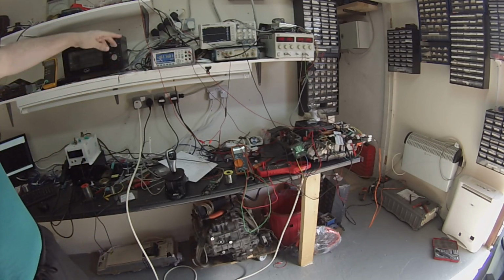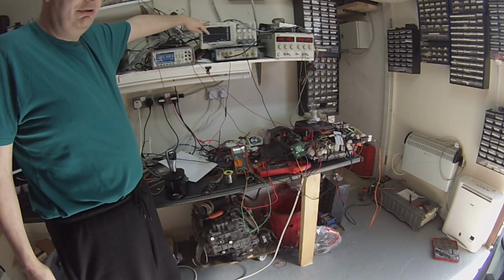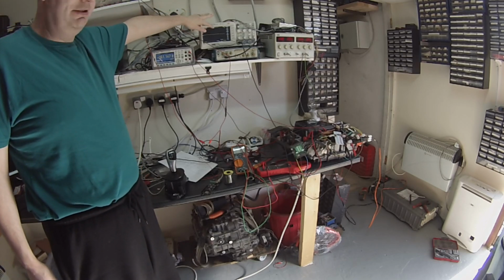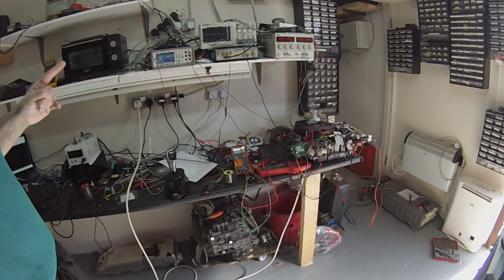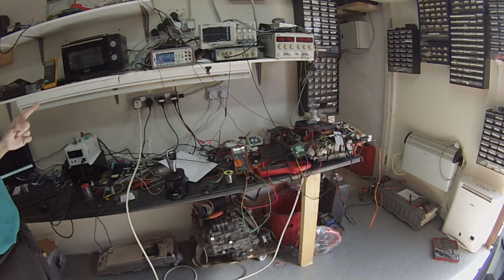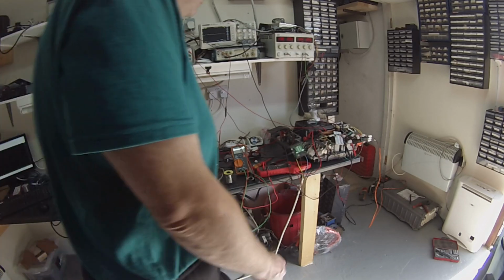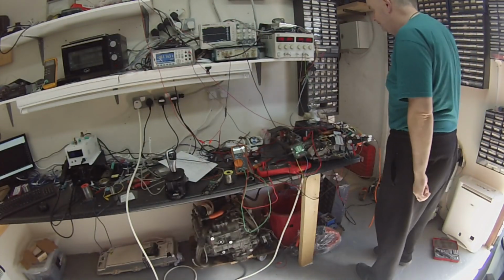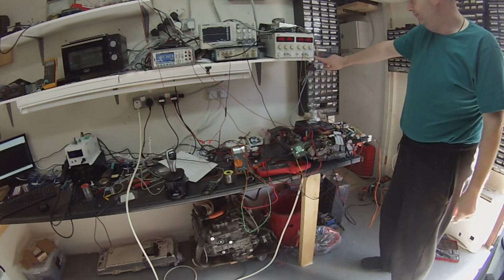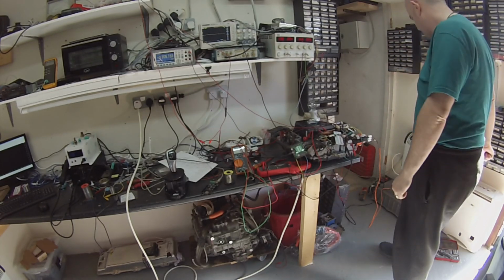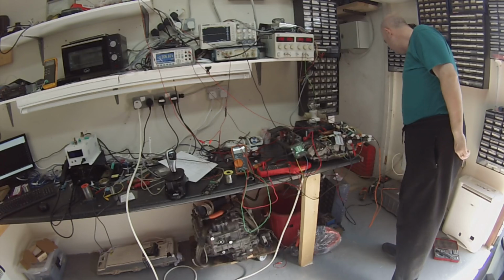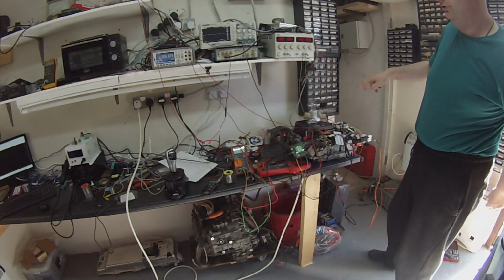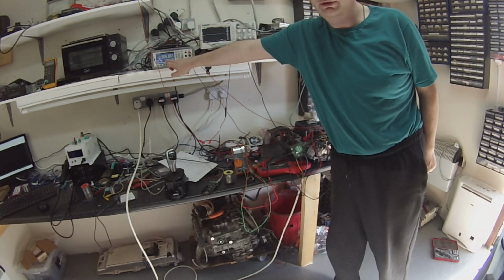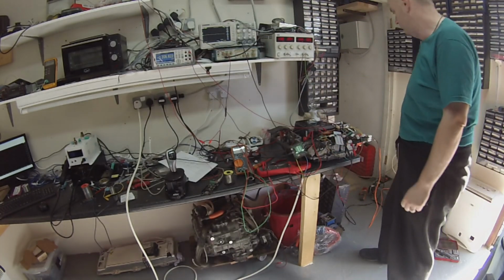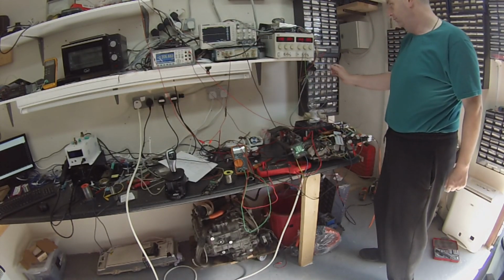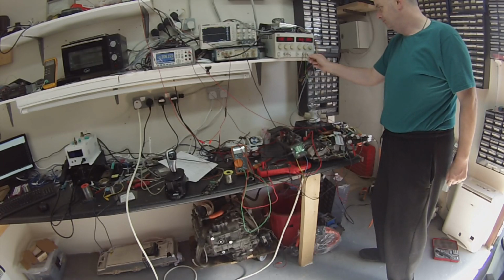So we want to start off by having our converter PWM at 0, which ensures the high side switch is fully on. Now, if we now initiate from the high voltage battery a pre-charge, we will have pre-charged the high voltage bus up to 205 volts, which is our battery voltage. So I'm going to close the main contactor.